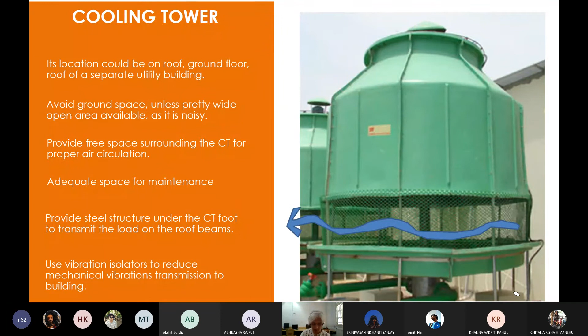Adequate space for maintenance. Provide a steel structure under the cooling tower, as I already said, because the weight is too much. It's like providing another water tank. Or you should have roof beams. Use vibration isolators to reduce mechanical vibration transmission to the building, if any. But generally there are, because sometimes we clean the water, sometimes water is brought inside, so all of that will create problems.